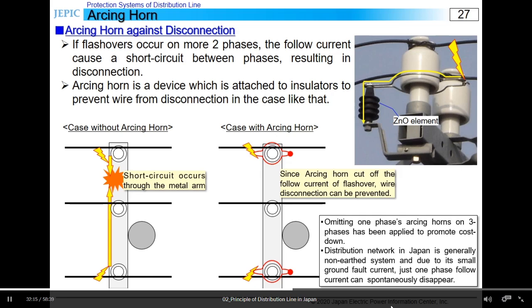To prevent such a case, arcing horns are attached to insulators as shown in the picture. An arcing horn consists of a ring-shaped metal part and a part containing the ZnO element. The discharge of a flashover can be separated from the insulator's surface, and its follow current can be cut off like a lightning arrester before the follow current transits to a short circuit.